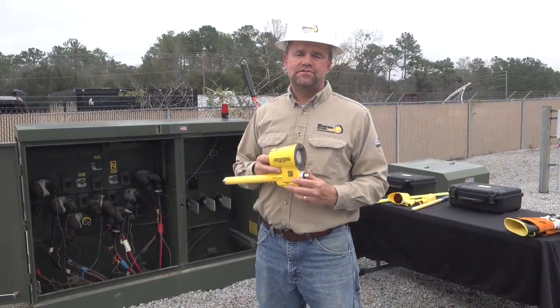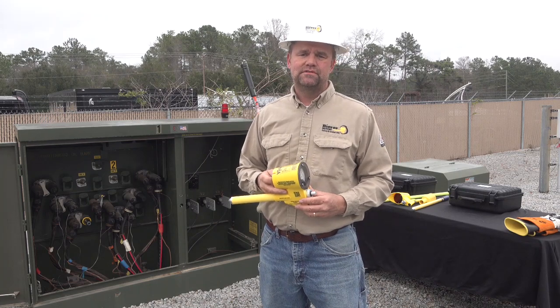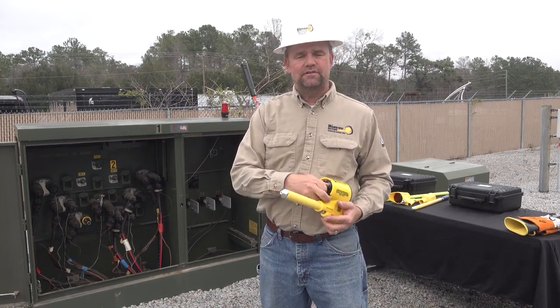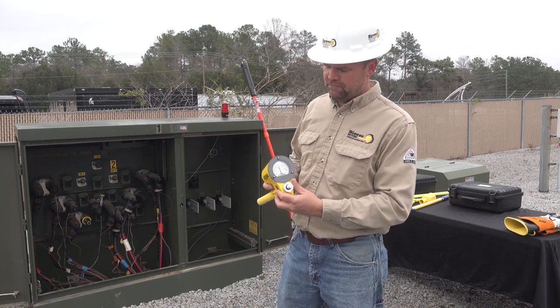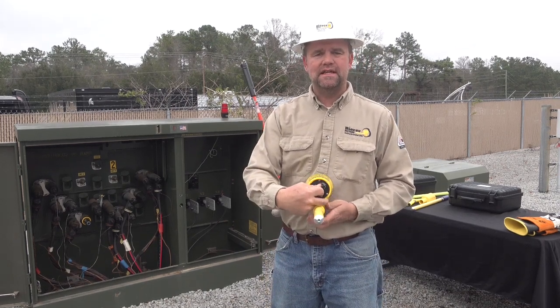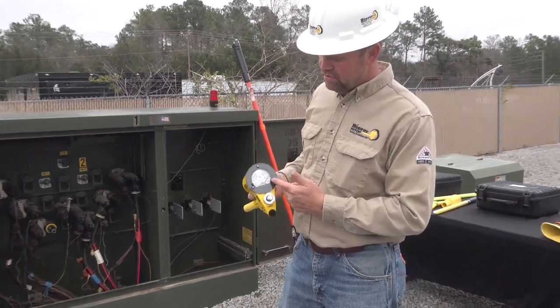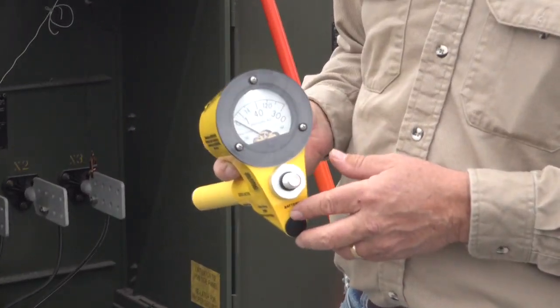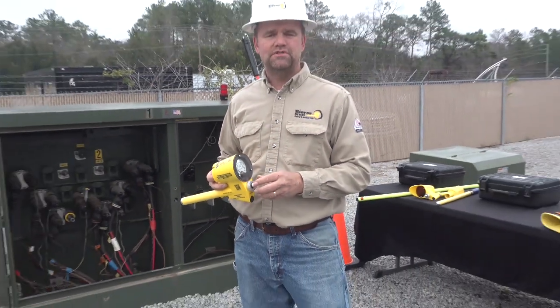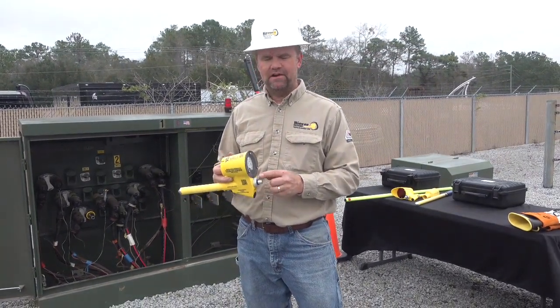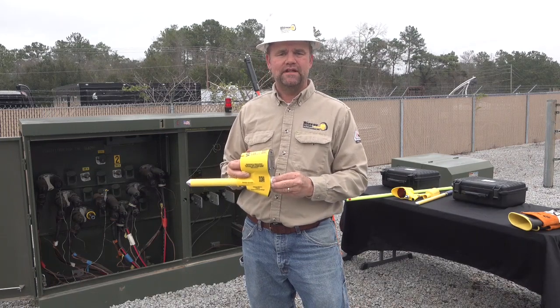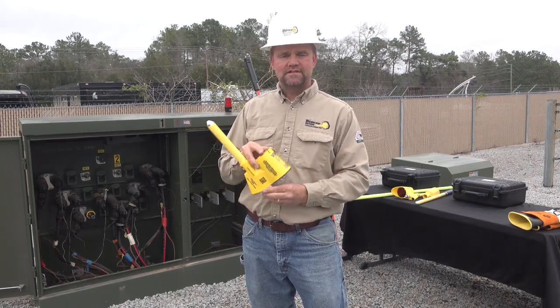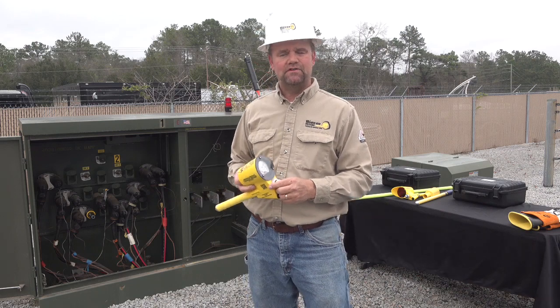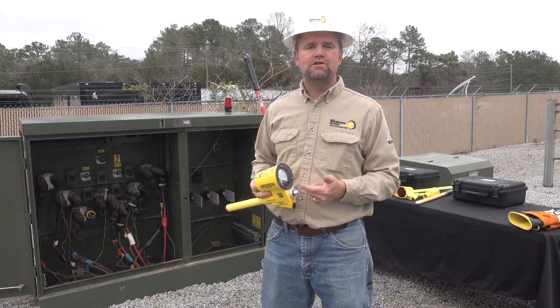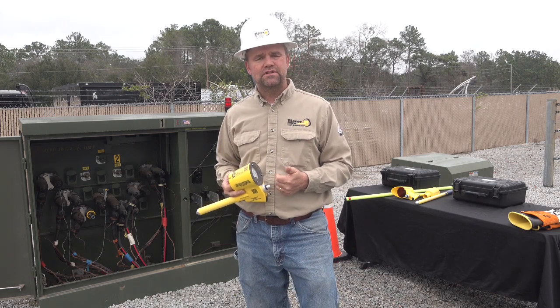Bierer highly encourages you to test the device before and after each use. The first test is the 5-position selector switch, and you have to physically hold the meter in the test position. Make sure you get near full deflection. If you do not get a full deflection, we encourage you to check the battery in the device. The 9-volt battery is located right here behind the live line tool fitting. Just thread this off. It has a 9-volt battery inside. Go ahead and replace that if you don't get a full deflection. If you still don't get a full deflection, we encourage you to send the device in for repair or calibration.